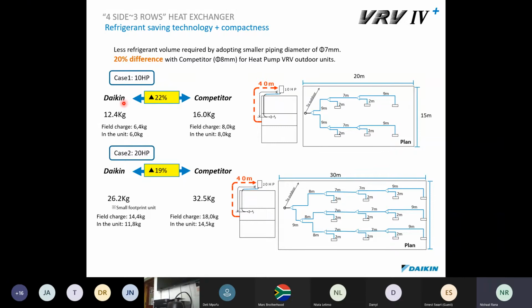And taking a competitor's machine to do the same duty, to do the same run, Daikin did a comparison, and our competitors use more charge. Now, how are they achieving higher efficiencies than us when the competitors' surface area of the coil is less, and on top of that, they're using more charge? There are ways to do it thermodynamically. You could go with very thin material to increase the heat transfer rate, but that's a story for a different day. This is just explaining the case study.